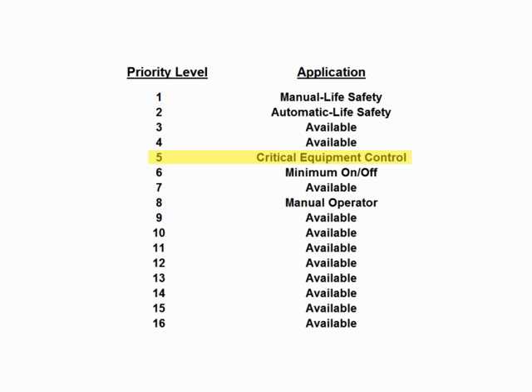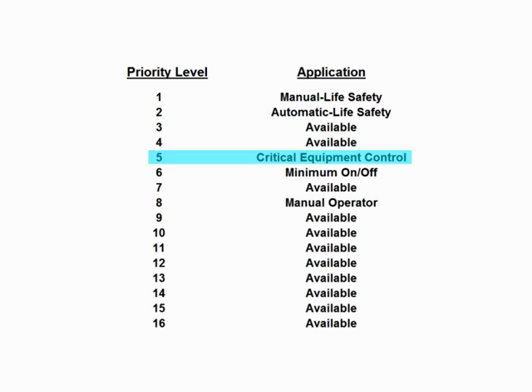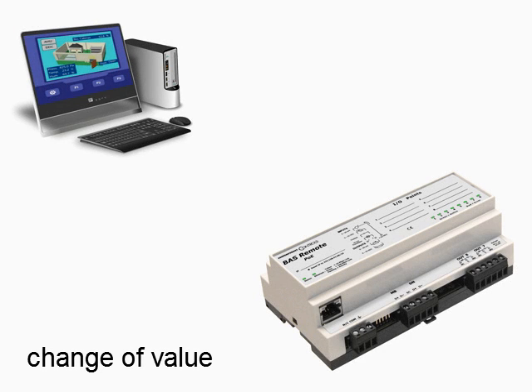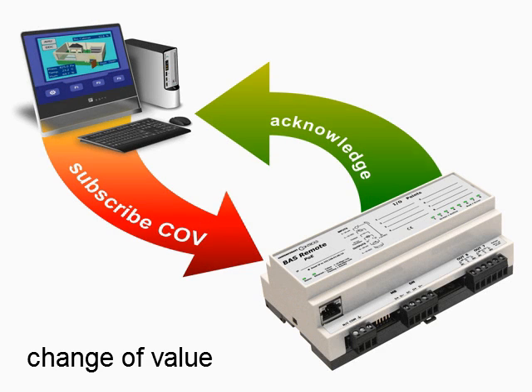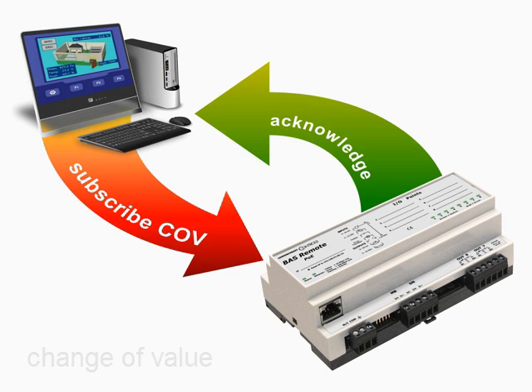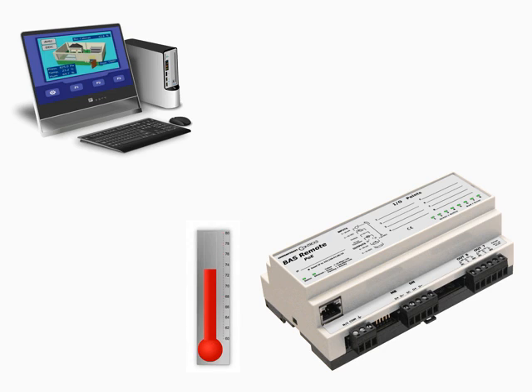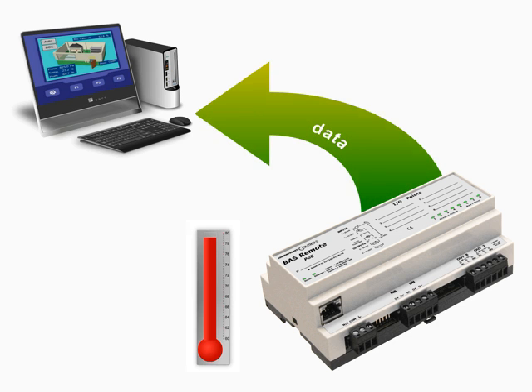If two clients are writing to the same server using the same priority level, the last value sent will be stored. To minimize data traffic, change of value (COV) is supported, where only values that change above a defined limit are sent. A client subscribes to the server device, and the server monitors the property and reports when the subscribed property exceeds the threshold range.